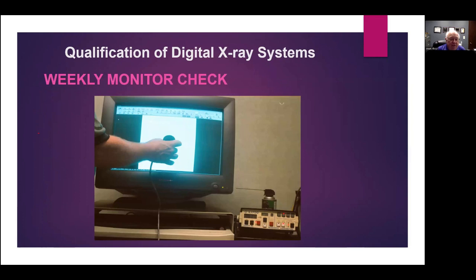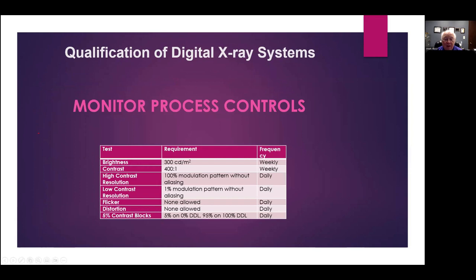Monitors typically have to be checked, and there are daily and weekly checks. So again, you have your calibrated photometer. Some of the tests they require: brightness, contrast, resolution, high resolution, low resolution, no flicker. Your monitor isn't flashing as you're looking at it, and then the contrast.